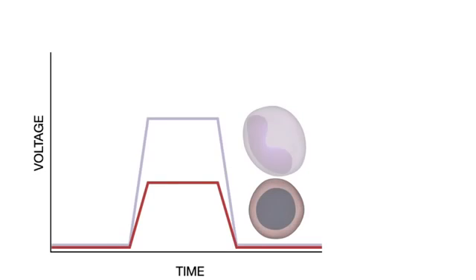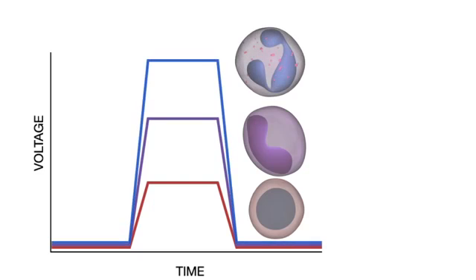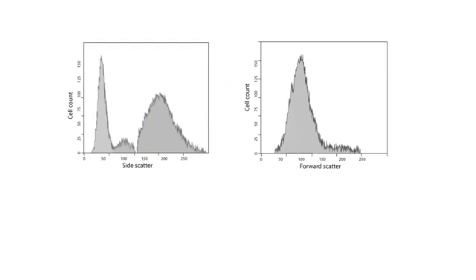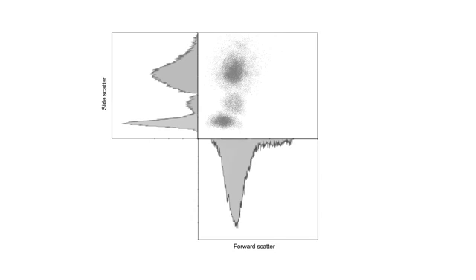Just like with forward scattered light, the flow cytometer converts the detected side scattered light into a voltage pulse, which is directly proportional to the amount of side scattered light. By analyzing the forward and side scattered data together, the researcher can understand a cell's size, shape, and complexity.